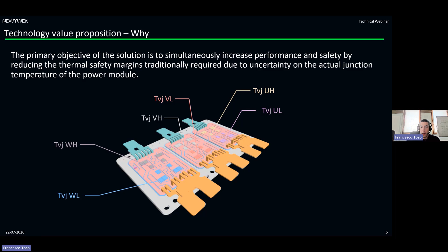For instance, between module A and module B, even if they are of the same supplier and family, you have manufacturing tolerances. Sometimes you also have variation of RDS on of 20% with respect to the datasheet, and that 20% variation is reflected in a 20% or even more variation in the power loss, and so different temperature and thermal behavior. Usually customers know that RDS on can change, and they take another thermal room, another safety margin on the estimation, once again leaving a lot of current on the table. So one of the technical challenges will be to be agnostic to manufacturing tolerances, and this can also be tackled by our software technology. We will see in a moment how.